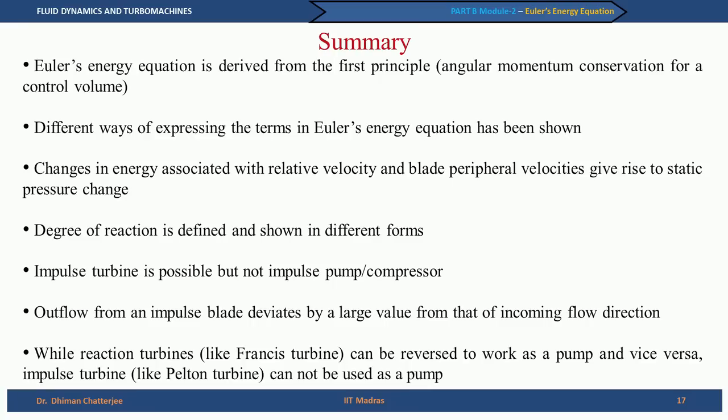While reaction turbines can be reversed to work as a pump and vice versa, that is, if you take a pump, you can make it rotate in the reverse direction, have the flow get admitted in the reverse direction, you will get a turbine. Maybe the turbine does not work as well as the pump would be, but such devices are not unheard of. In fact, there are applications called pump as turbine or PAT, which are used or proposed as low cost power generation method in remote areas. However, impulse turbine like Pelton turbine cannot be used as a pump.